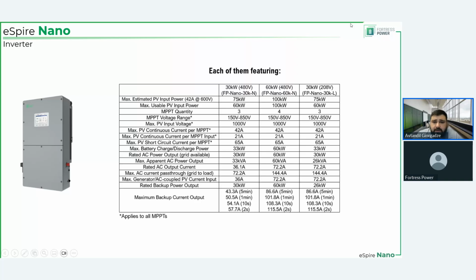Just quickly, let's go over what we have in terms of the inverters. We have 3 models available. One of them is a 30 kilowatt 480 volt inverter. We also have a 60 kilowatt 480 volt inverter, and we also have a 30 kilowatt 208 volt inverter. And this 30 kilowatt 208 volt inverter is the one that can do high leg delta, but with no backup. The other 2 are strictly dedicated to what they show, and also certain other variations depending on the area in which it will be deployed.